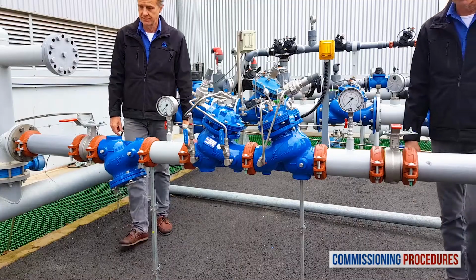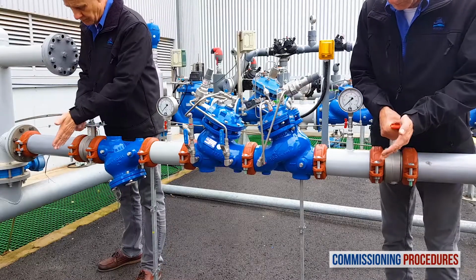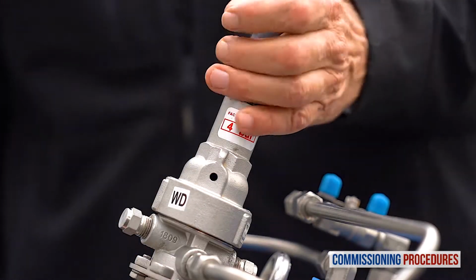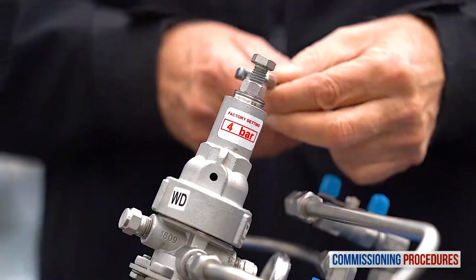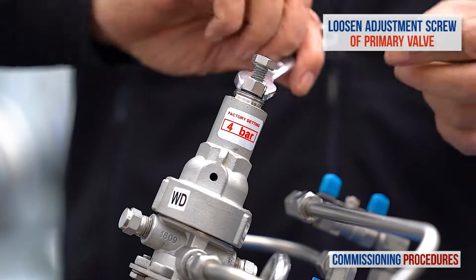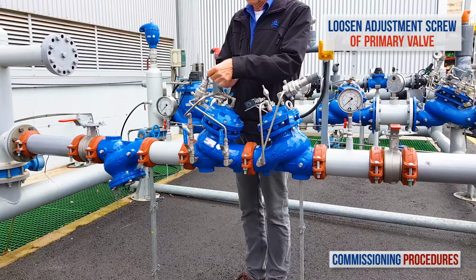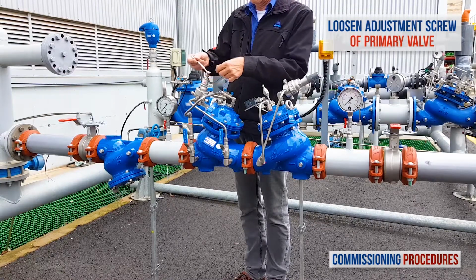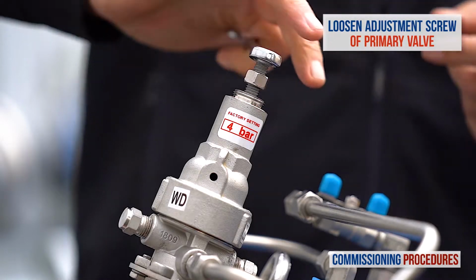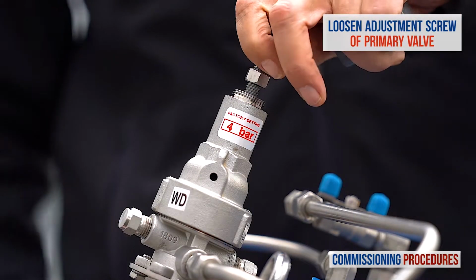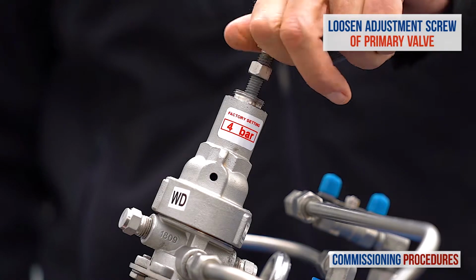All right, now let's talk about the other case, which is when the factory set pressure level doesn't meet your requirements and you need to adjust the station's downstream pressure. In this case, all you need to do at this point is to prepare for it. First off, verify that both isolation valves are closed. Now remove the protective cover from the pressure reducing valve's pilot. Release the locking nut screw and completely unscrew counterclockwise the primary reducing valve's pilot adjustment screw until it becomes loose. This allows us to later calibrate the pressure at the outlet of this valve to the required value.